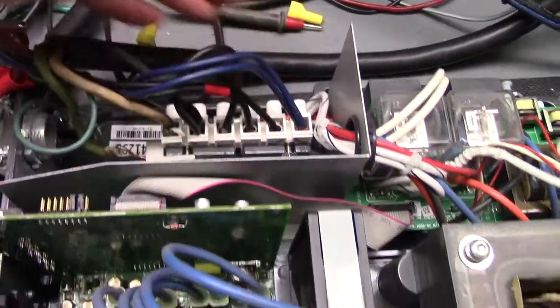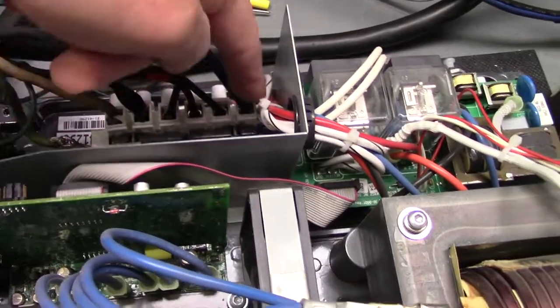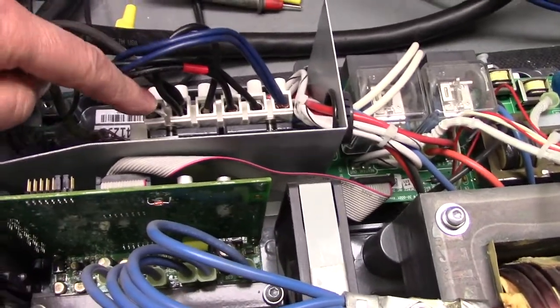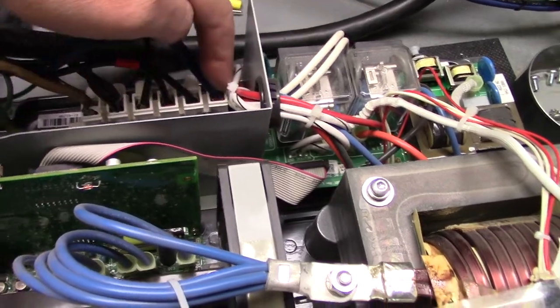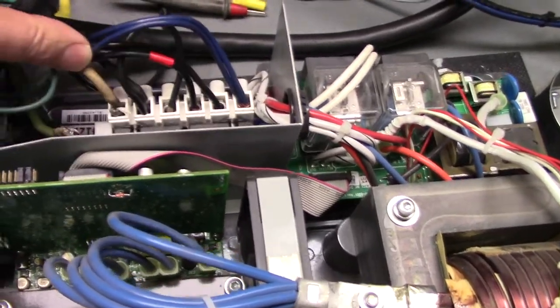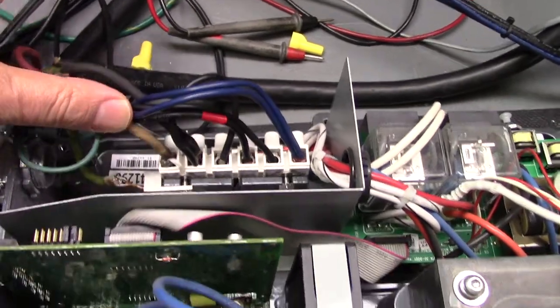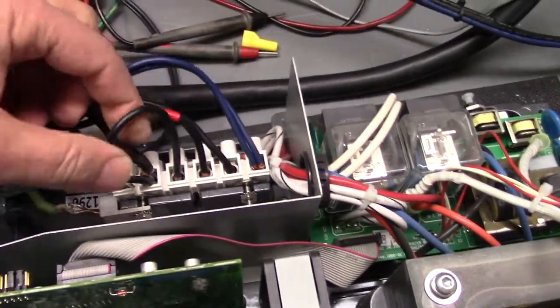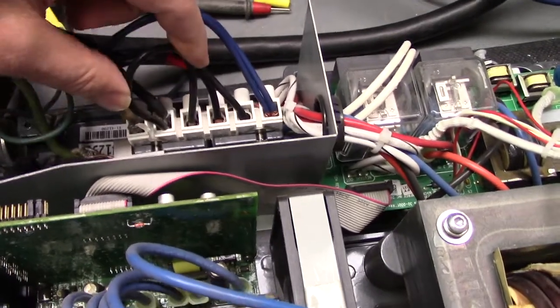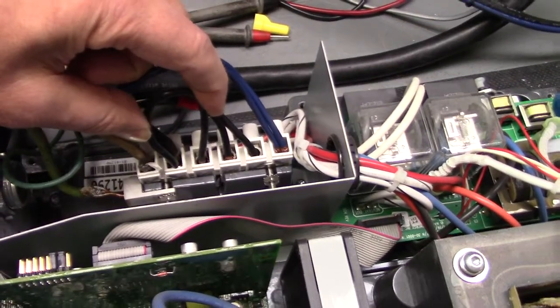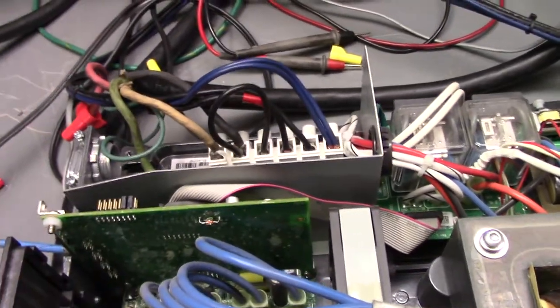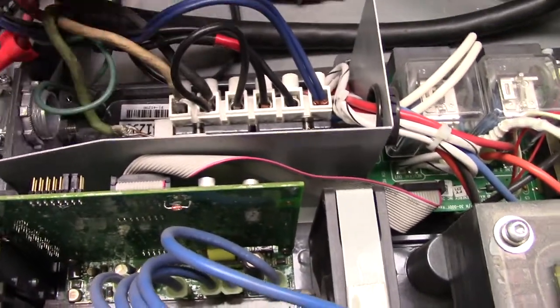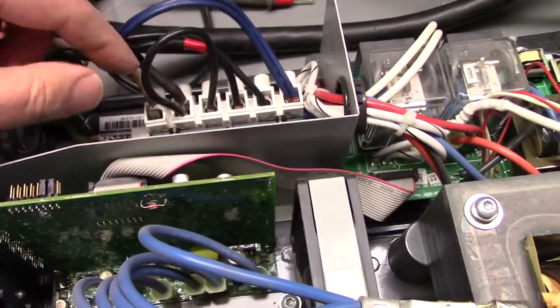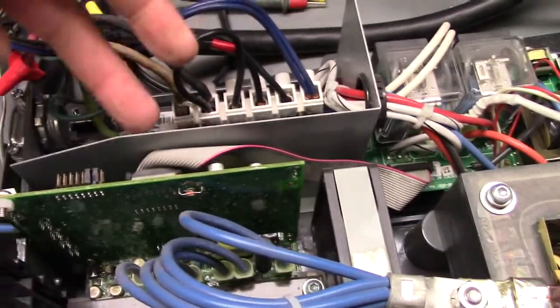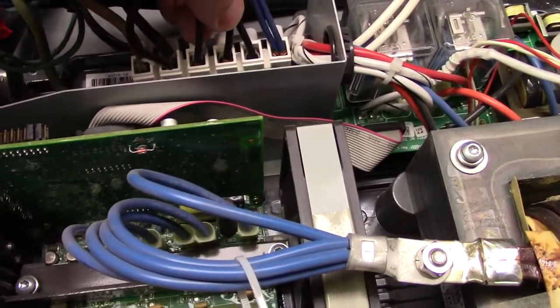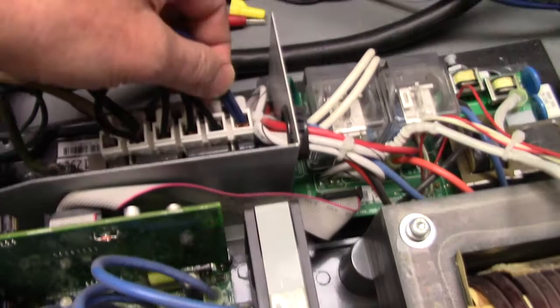Oh, you have the terminal strip with 3 inputs, 3 outputs. So you have a neutral and an L1, L2, and then a neutral, L1, L2. The inputs can be configured a couple different ways. This one that I have right now, you have your neutral and the 2 phases, L1 and L2, just jumped together. And if you have a 30 amp service, this is how you'd connect it. It just goes straight through as 2 120 volt circuits. Comes out as 120 volt circuits in reference to your neutral.